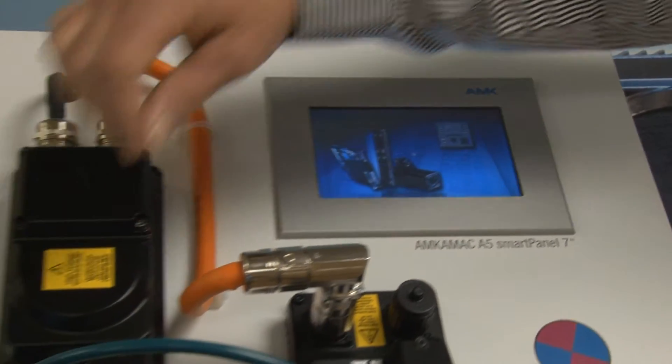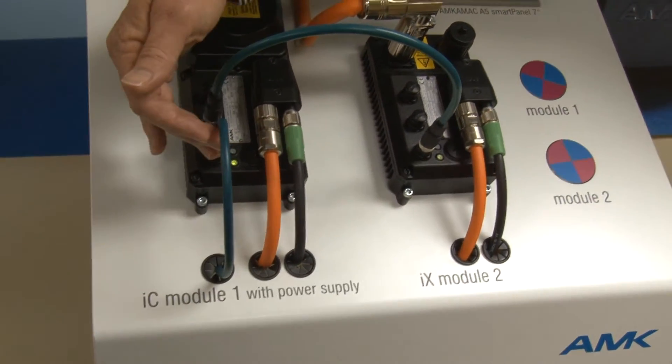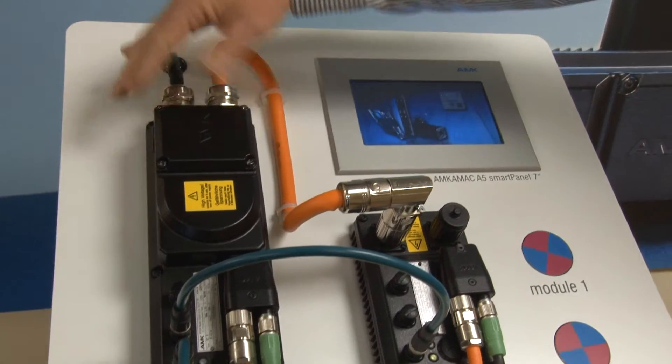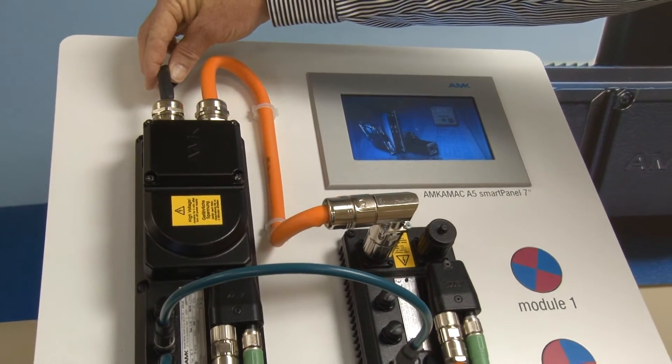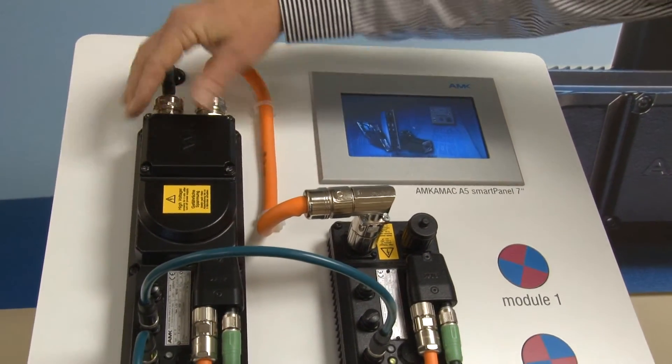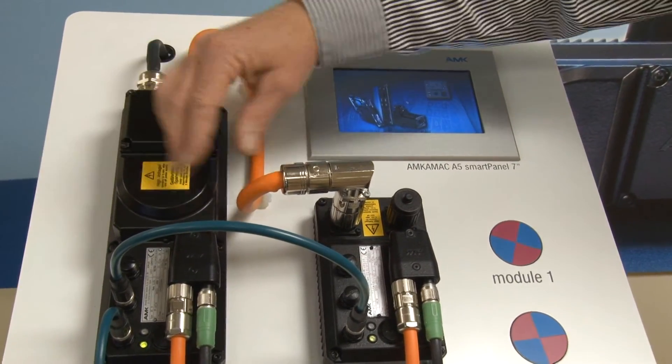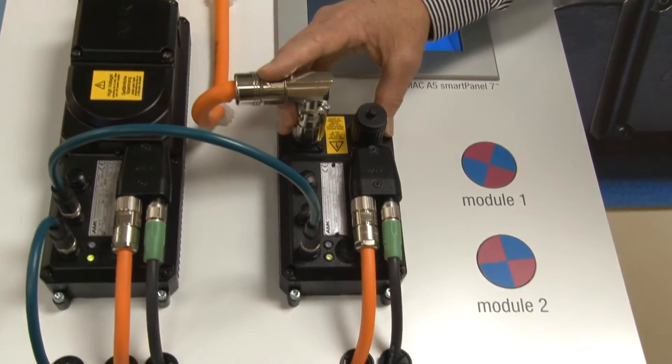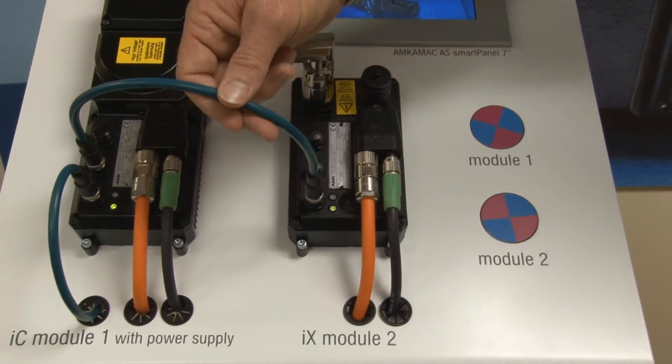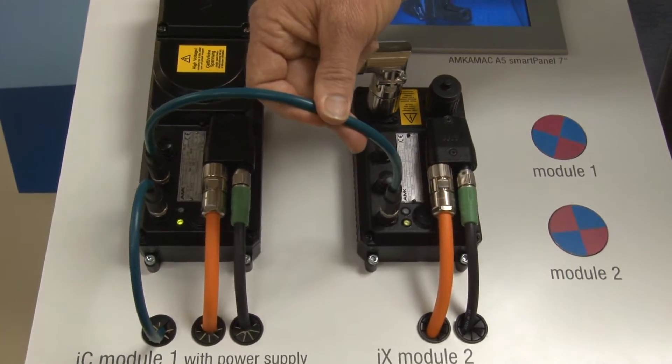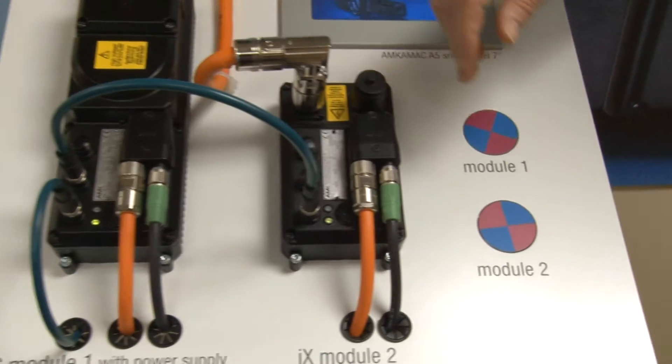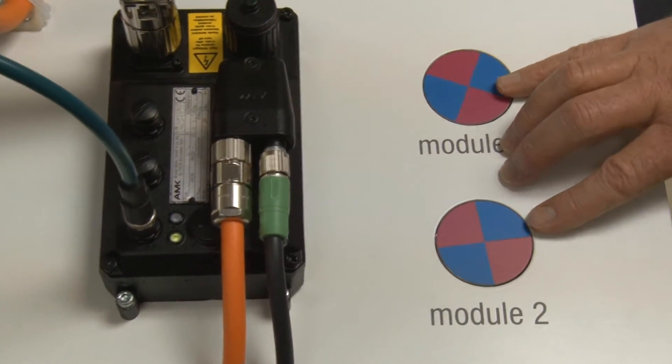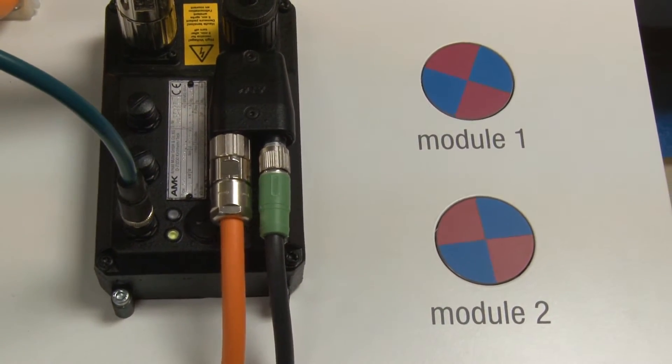The EtherCAT from the A5 is connected to the first servodrive, which is an IC5 decentralized servo with AC voltage input. The IC produces the DC bus voltage for use internally as well as for providing power for other units such as this IX servodrive. The EtherCAT is daisy-chained from unit to unit. The motors we are using are DT-type synchronous servomotors with single-turn absolute encoders.